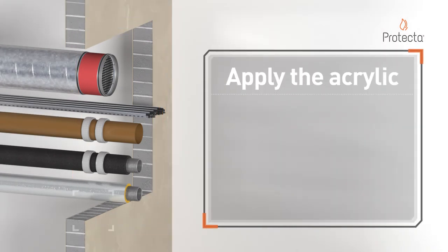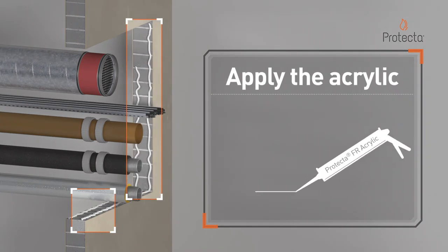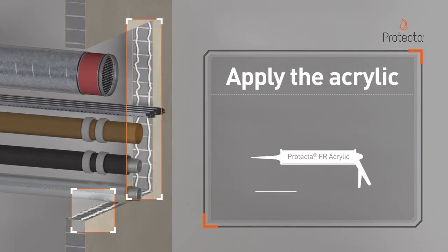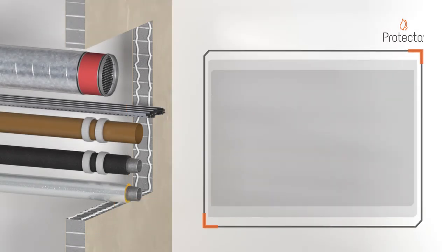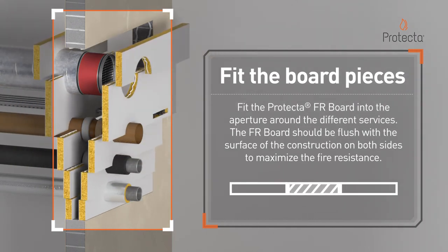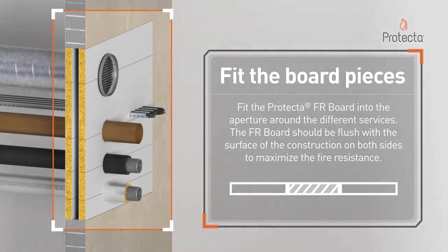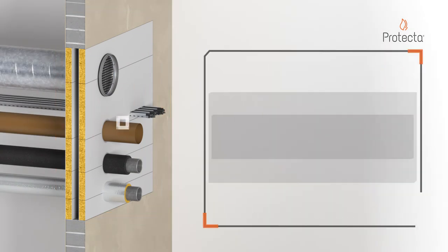Apply Protecta FR acrylic. Fit the Protecta FR board into the aperture around the different services. The FR boards should be flushed with the surface of the construction on both sides to maximise the fire resistance.